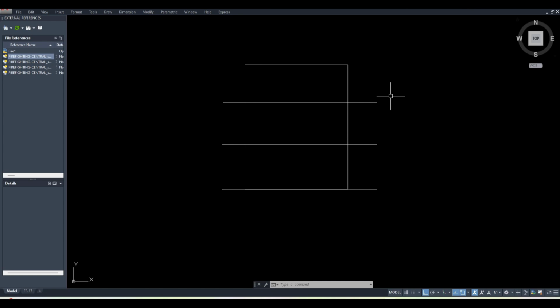How many zones, five zones, or no? If we divide, suppose, listen once again. There is a requirement that each floor has to be a separate zone, regardless of the area. If it is a separate floor, it must be a zone. There is no question.